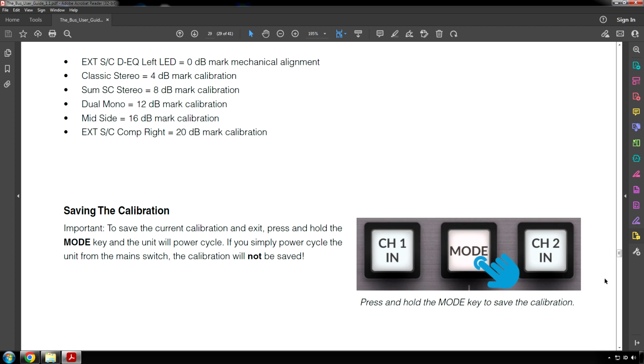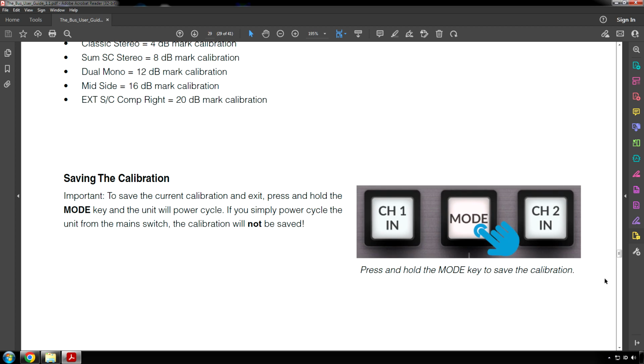Saving the calibration. Important. To save the current calibration and exit, press and hold the mode key and the unit will power cycle. If you simply power cycle the unit from the mains switch, the calibration will not be saved.